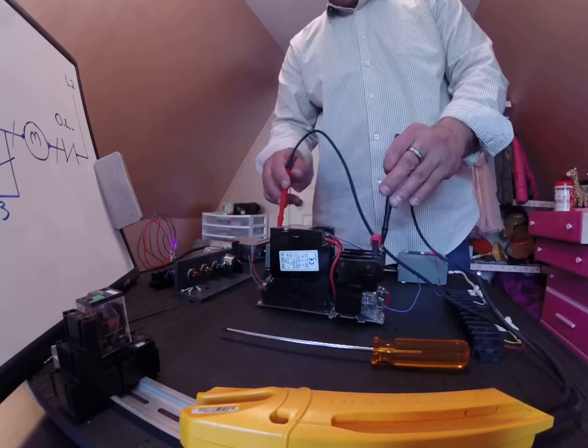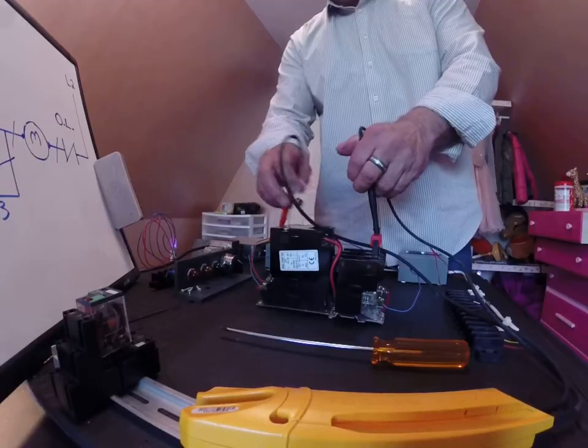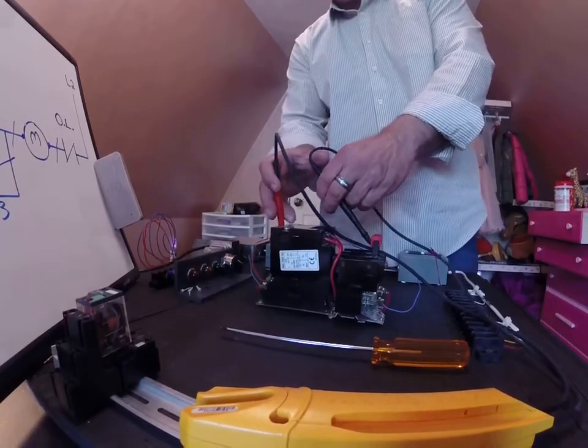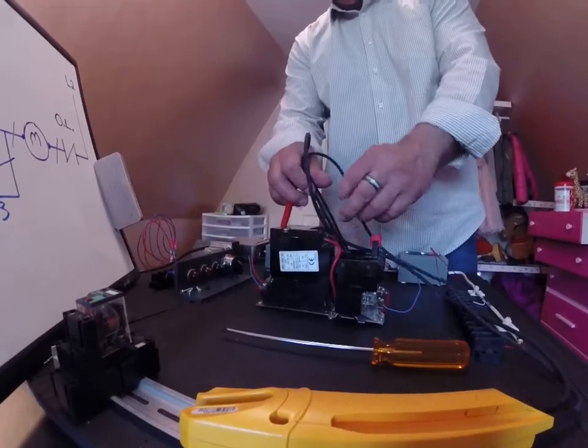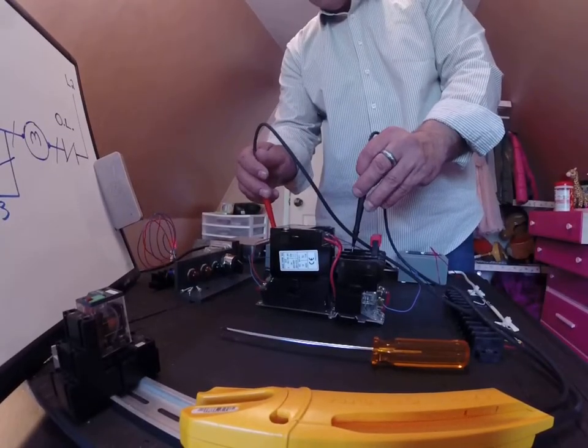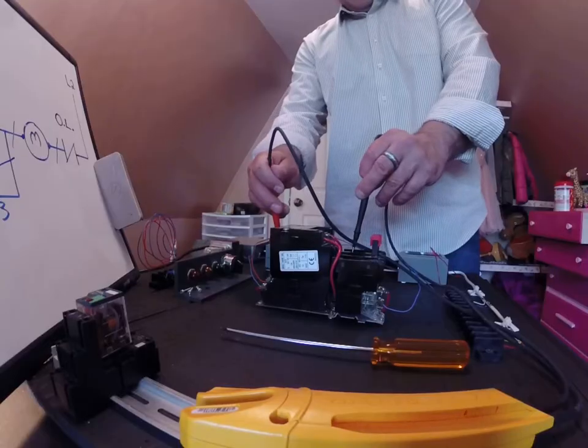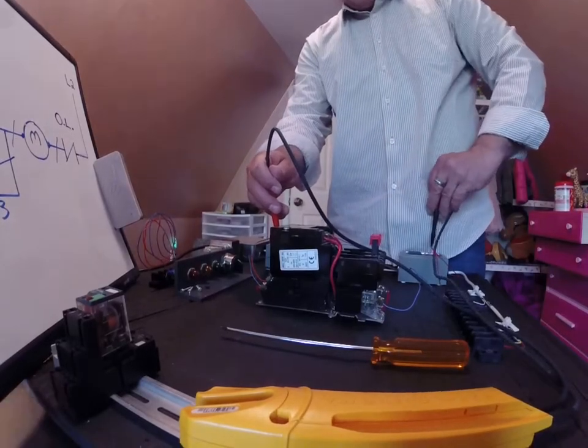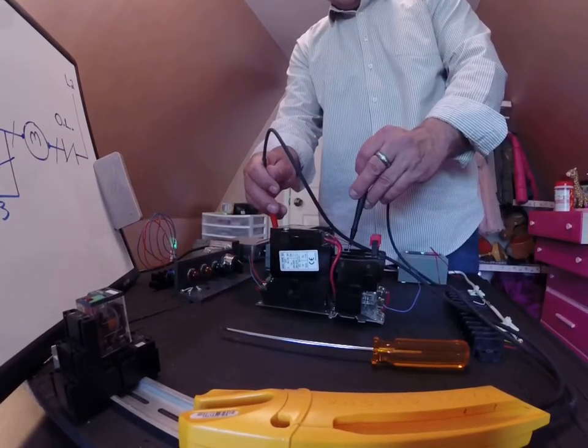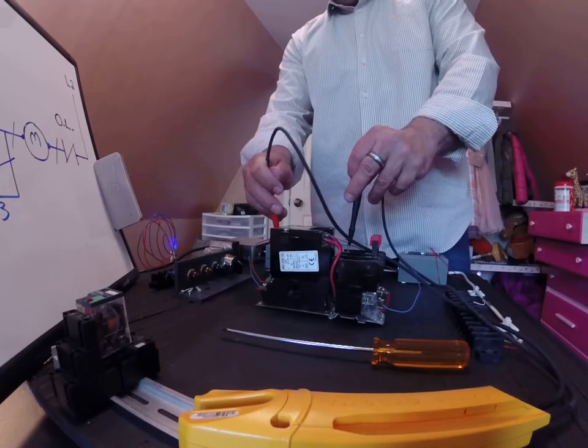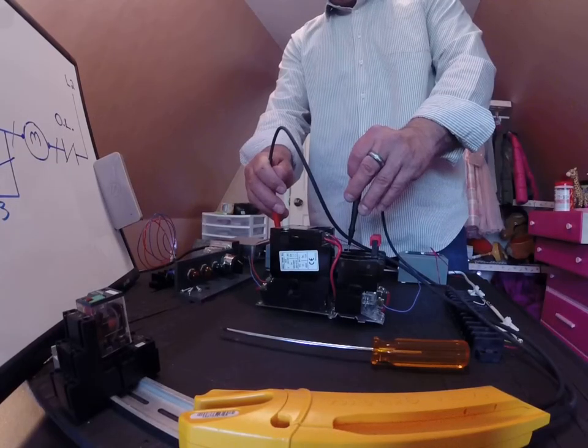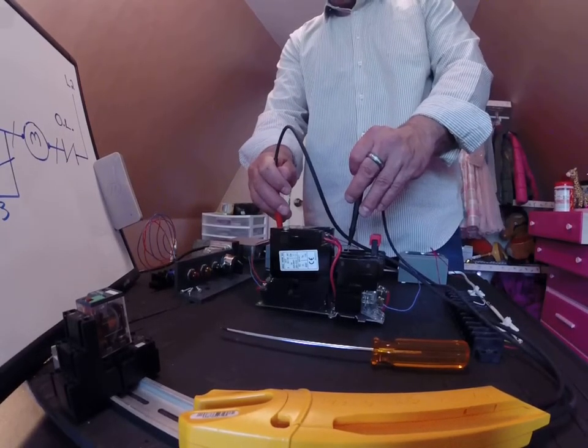If I hold it here and hit the stop button you'll see that I lost continuity between my incoming and outgoing. So you know one way to determine if you've got power is obviously make sure your motor starter is pulled in.